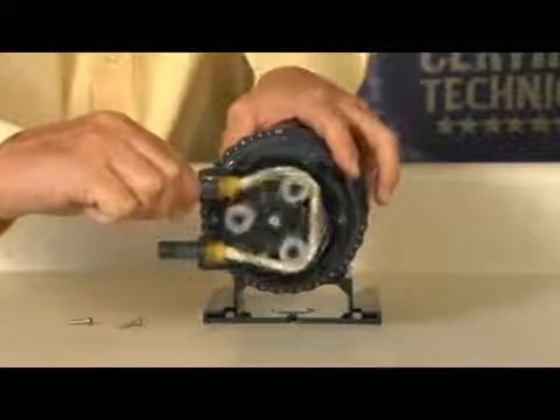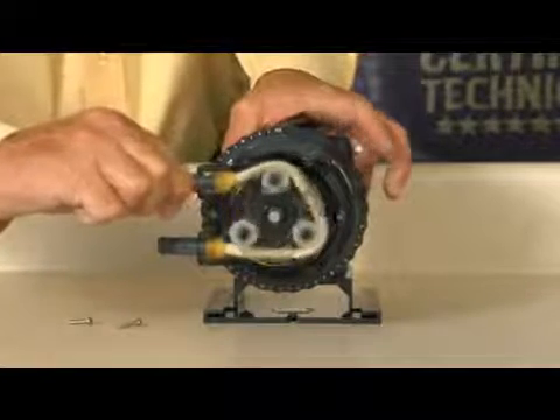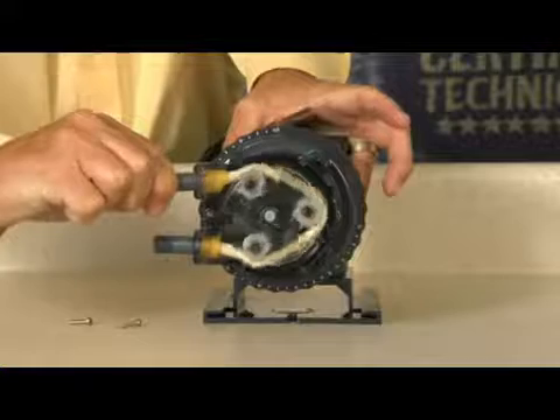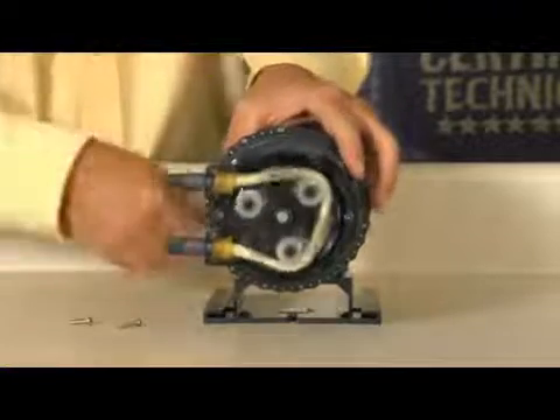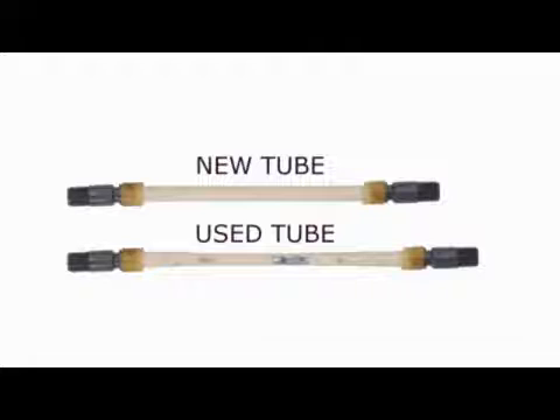While holding the tube fitting firmly, without pulling, allow the rollers to stretch the tube into place while guiding the tube into the slot. Turn the pump off. A used tube will have stretched approximately 3/4 of an inch, and the new tube will appear to be stiff and short, which is why it's important to follow the directions to allow the rollers to stretch the tube into place.